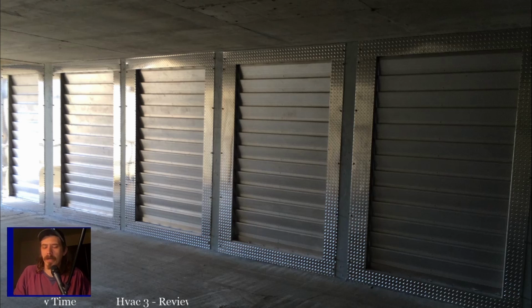You know what I mean? If you look at this curve, the temperature is 32 degrees and the thermistor is supposed to be at 33,000 ohms. And it's really at 60,000 ohms, even though we know the temperature is 32 degrees. It's not out of calibration very often. Generally, it's going to either be shorted, it's going to be open, or it's going to be operating properly. Doesn't mean you won't run across that sometime, but it's pretty rare.